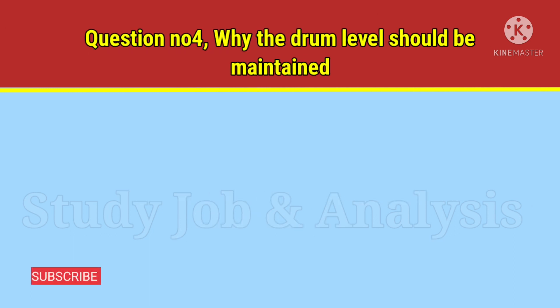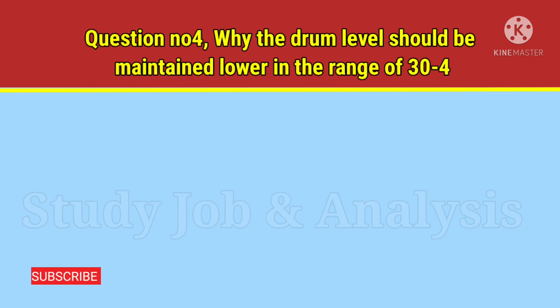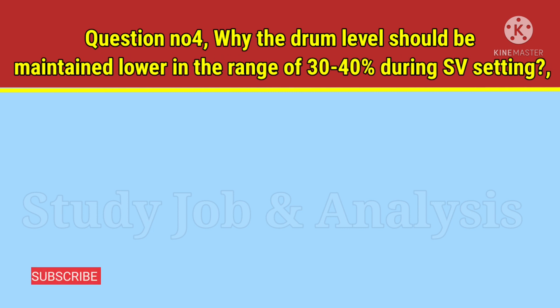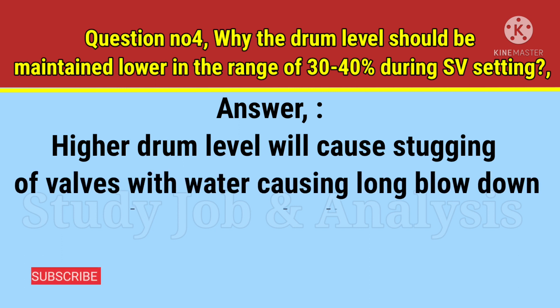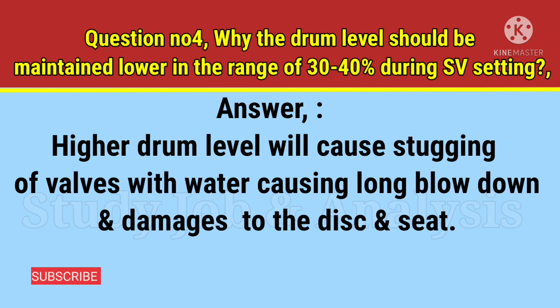Question number four: why should the drum level be maintained lower, in the range of 30 to 40 percent, during safety valve setting? Answer: A higher drum level will cause wiredrawing of valves with water, causing long blowdown and damages to the disc and seat.